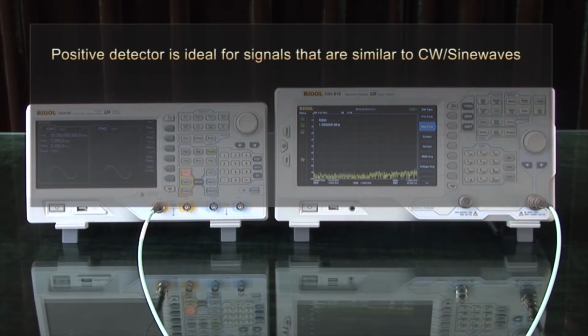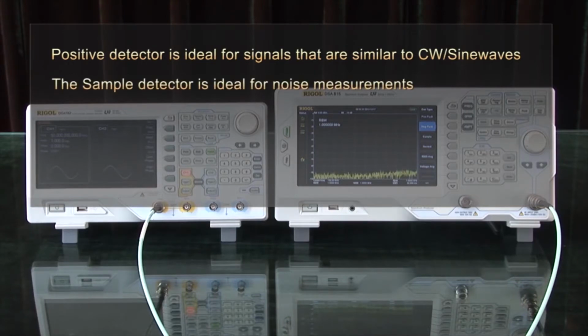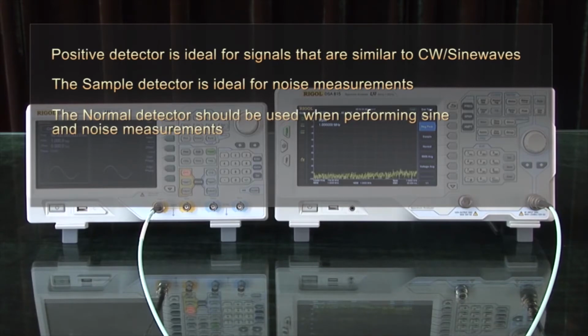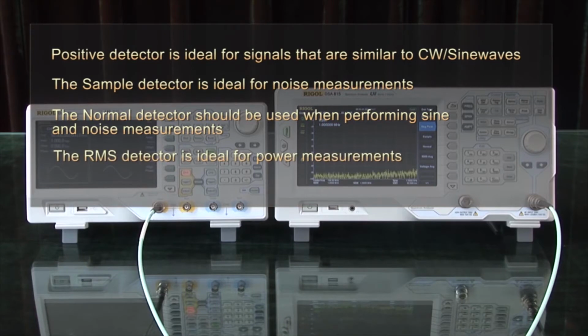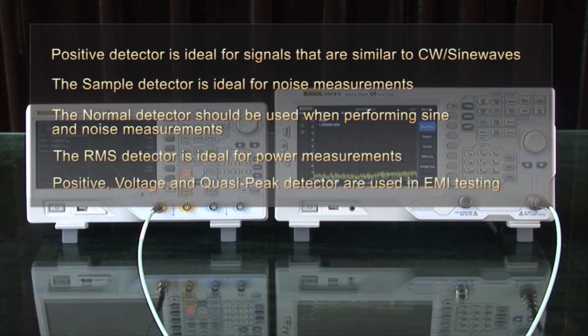Here are the key points. Positive detectors are ideal for signals that are similar to CW or continuous wave and sine waves. The sample detector is ideal for noise measurements. The normal detector should be used when performing sine and noise measurements concurrently. The RMS detector is ideal for power measurements. Positive, voltage, and Quasi-peak detectors are primarily used in EMI testing.